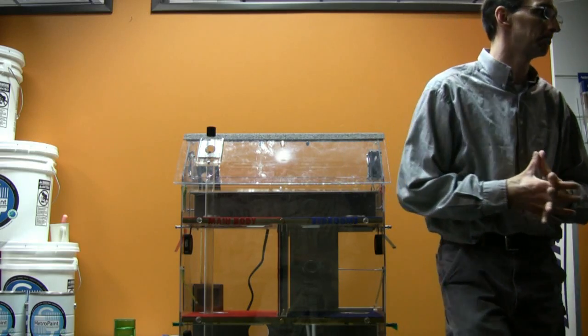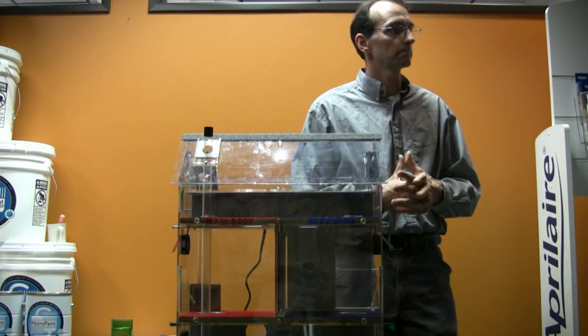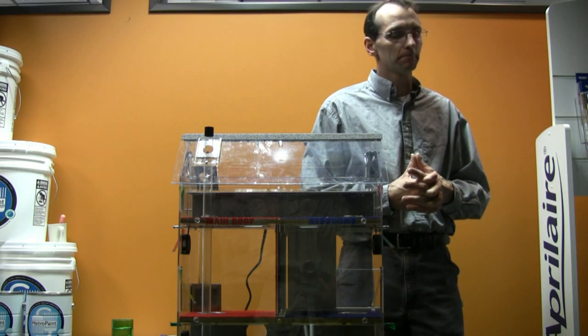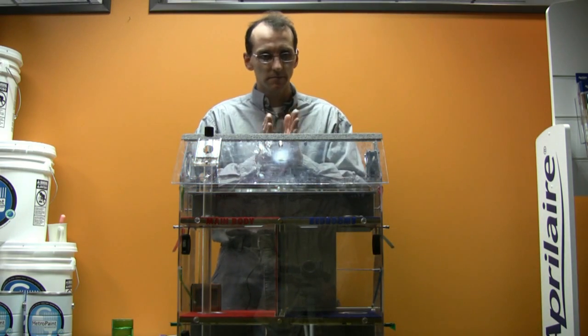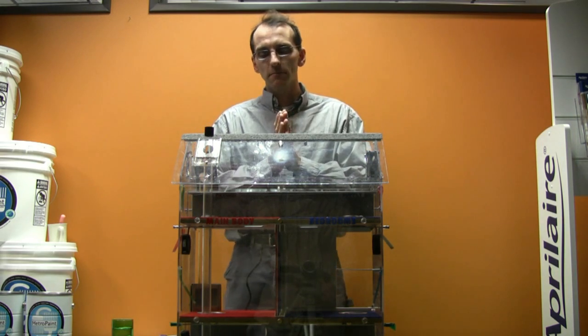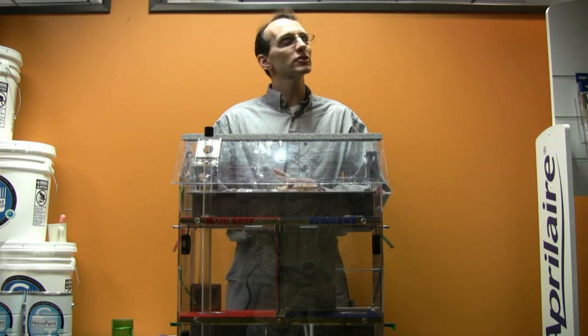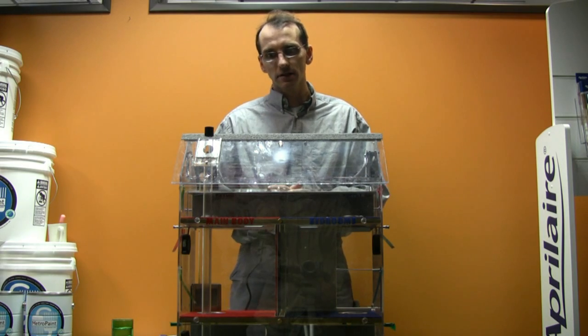Again, the reason we don't want this is that the carbon monoxide then might enter the living space. Is that the reason? Right. It has nothing to do with the moisture around the outside of the building or anything like that. No, this is combustion. We're testing combustion safety, especially for an open draft water heater.